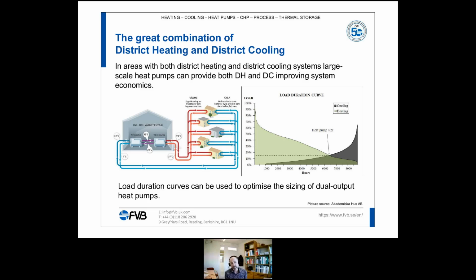And on the right-hand side, you can see load duration curves. It's for the district heating and district cooling. And when you combine these two, you see the time period where you can run the heat pump on both cooling and heating, and it's the dark gray area there. It also tells you how you can size the heat pump. And in this example, the heat pump would provide approximately 50% of the district cooling and 20% of the district heating.